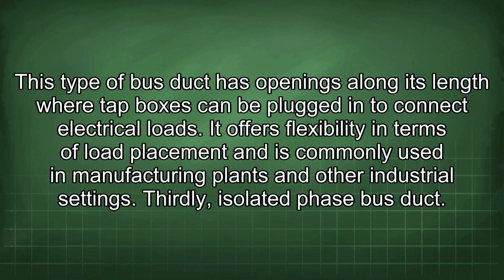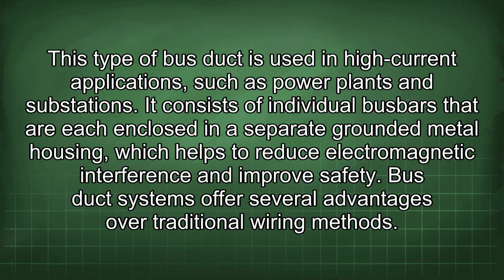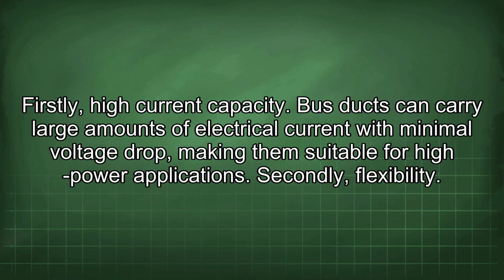Thirdly, isolated phase bus duct. This type of bus duct is used in high current applications such as power plants and substations. It consists of individual bus bars that are each enclosed in a separate grounded metal housing, which helps to reduce electromagnetic interference and improve safety. Bus duct systems offer several advantages over traditional wiring methods. Firstly, high current capacity. Bus ducts can carry large amounts of electrical current with minimal voltage drop, making them suitable for high power applications.